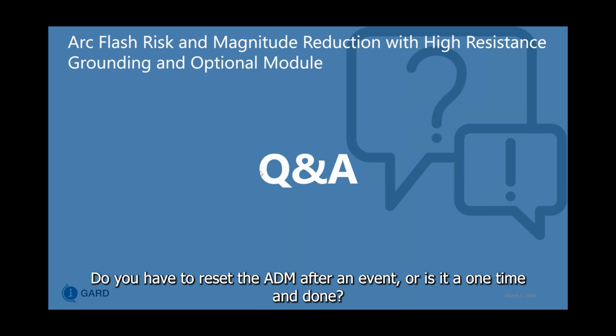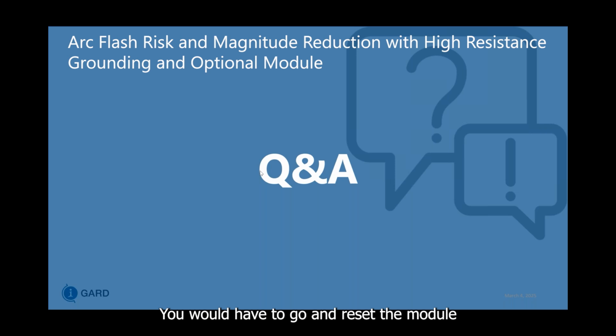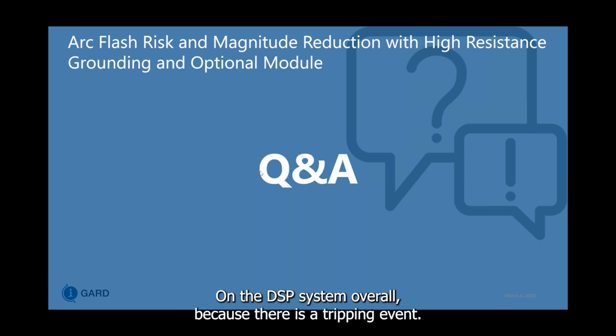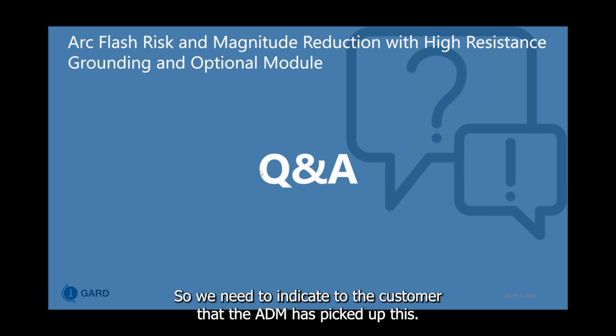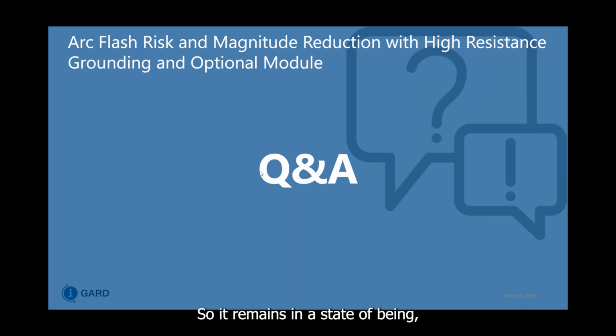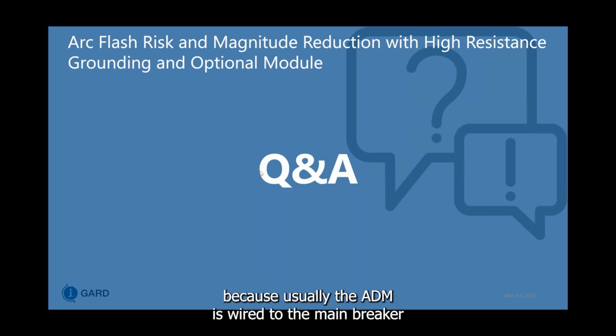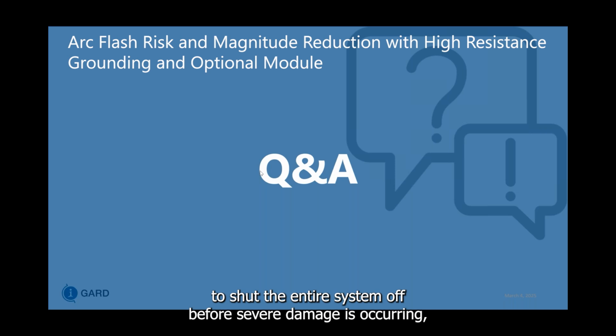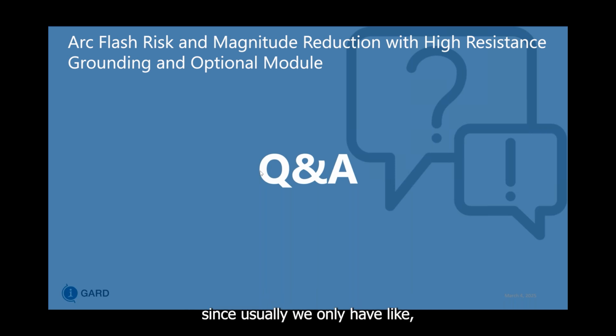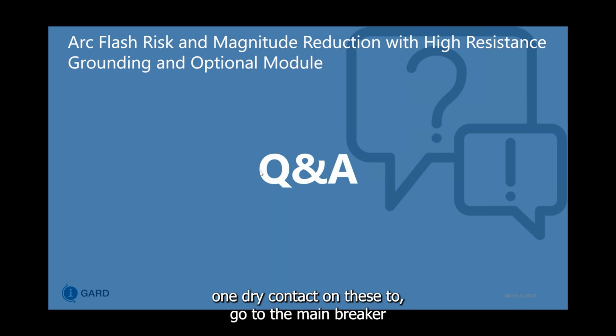Do you have to reset the ADM after an event, or is it a one-time and done? You would have to go and reset the module on the DSP system overall because there is a tripping event. So we need to indicate to the customer that the ADM has picked up this, so it remains in a state of being active and indicating that a fault has occurred. Your system at this point should be completely offline because usually the ADM is wired to the main breaker to shut the entire system off before severe damage is occurring, since usually we only have like one dry contact on these to go to the main breaker or the upstream breaker.